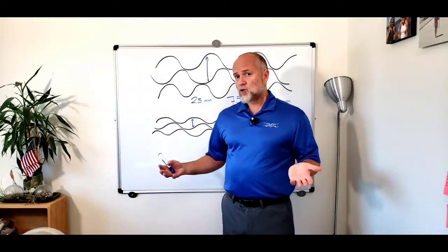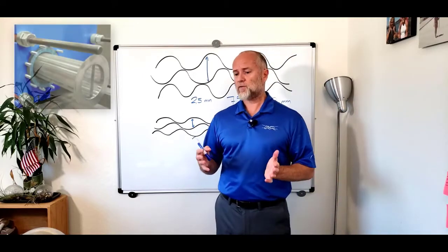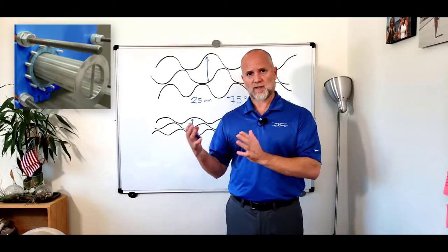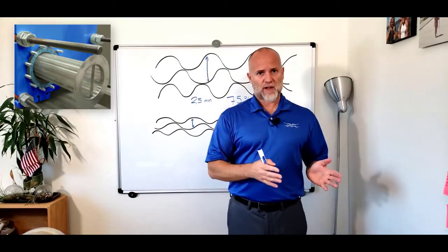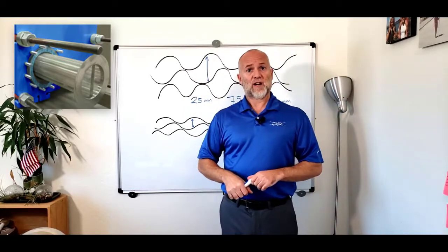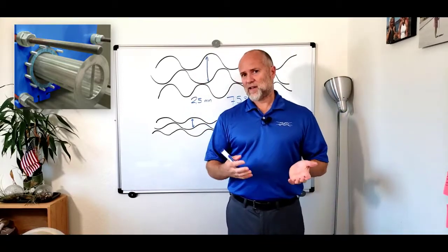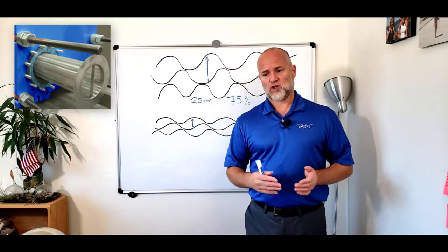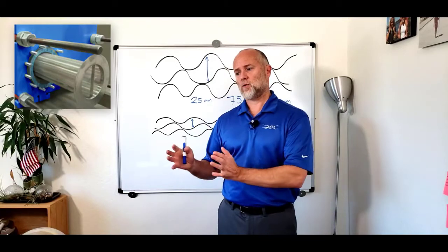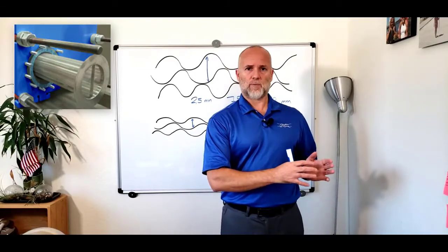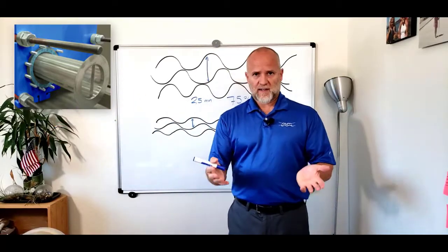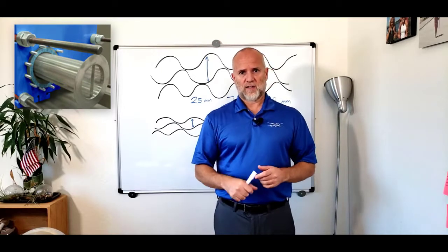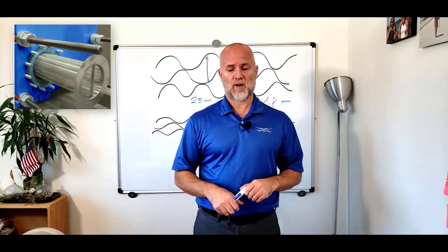The third solution, of course, is the port filter. The port filter comes with the heat exchanger, so it's provided by the vendor, so you don't have to worry about matching the mesh with the size of your channels, because that is done by the vendor. And it has another advantage: it is inside of the heat exchanger. Another important concept is that you position your strainer as close as possible to the heat exchanger so you don't have any contaminants after the strainer. Here you can see a picture of a port filter, and you see that it is embedded inside of the heat exchanger.